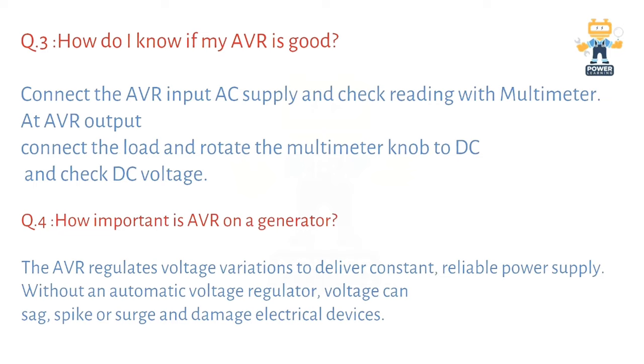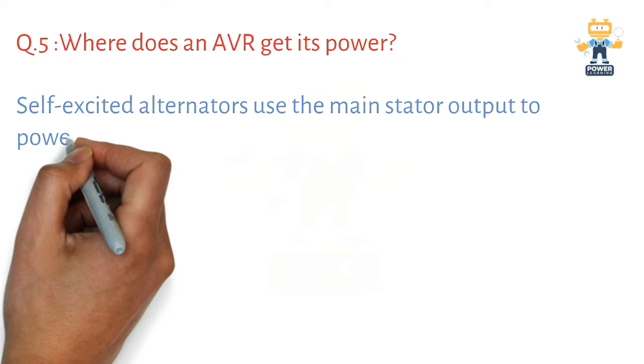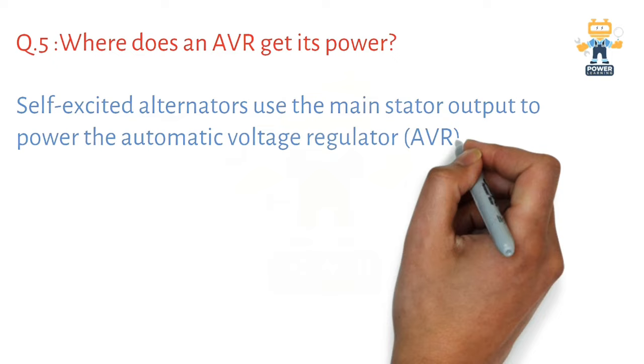Question number five: Where does an AVR get its power? Self-excited alternators use the main stator output to power the automatic voltage regulator AVR and provide power to the excitation system.